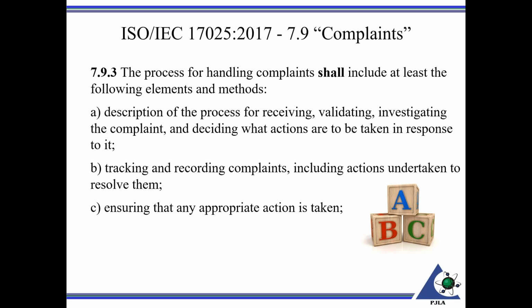The second part of this is including taking actions to resolve them, along with C: ensuring that any appropriate action is taken, which could be corrective action, or perhaps just correcting the issue at hand. An example I like to give would be a report that has a wrong serial number, or a sample that got transposed. Something like that could be corrected easily enough. However, correction does not prevent a reoccurrence. If you have 5 or 6 calls that come in a short period of time, then perhaps formal corrective action would be needed in that instance.